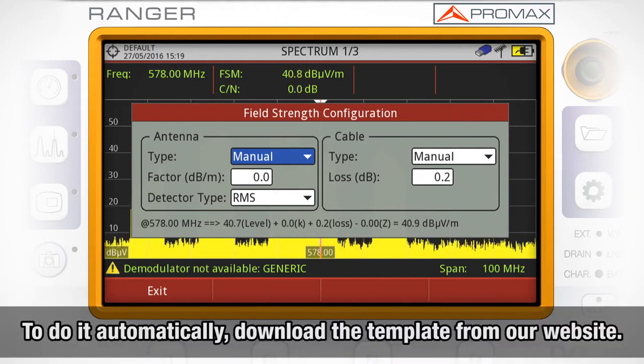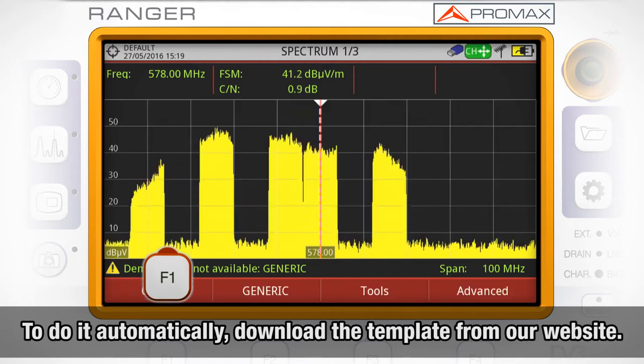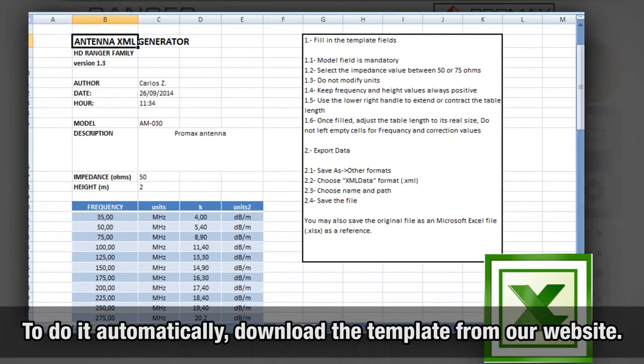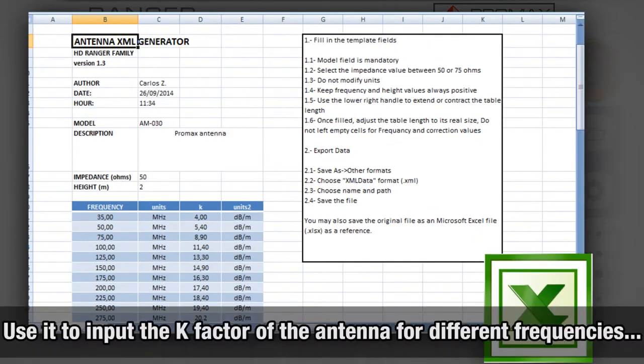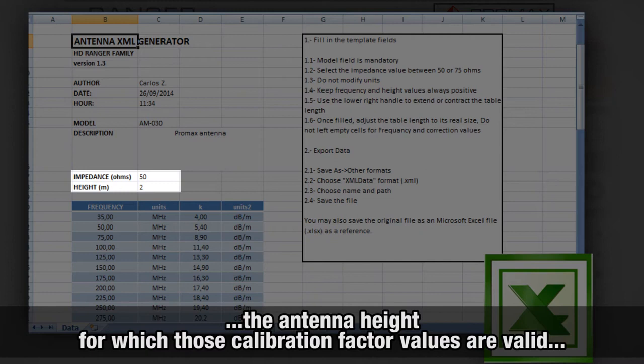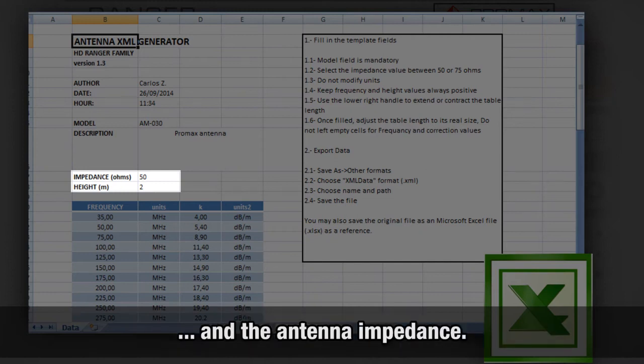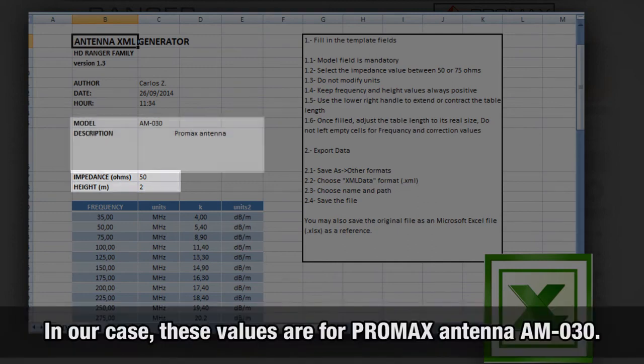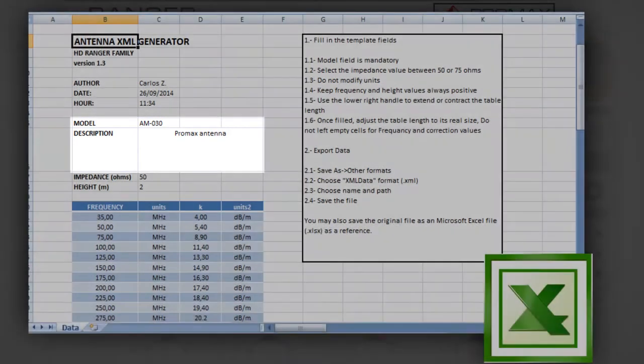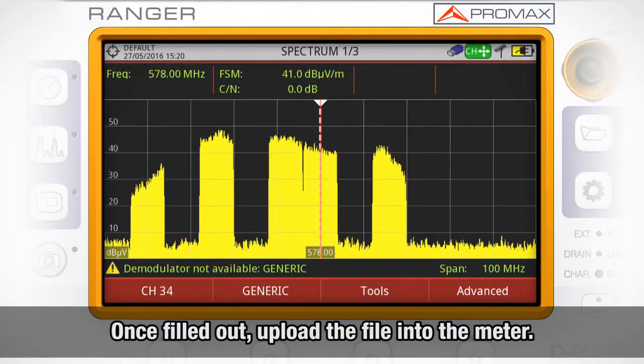If we want to do it automatically, we will need to download a template from our website, which we will use to input the K-factor of the antenna for different frequencies, the antenna height, for which those calibration factor values are valid, and finally, the antenna impedance. In our case, we have input the K-factor calibration data for Promax antenna AM030. Once filled out, this file needs to be uploaded into the meter.